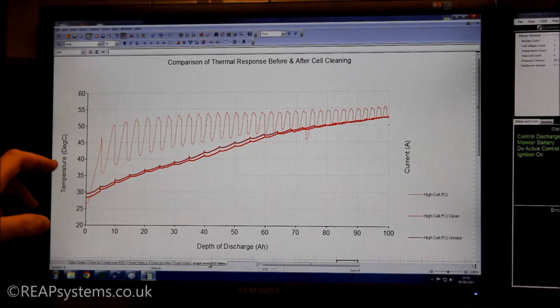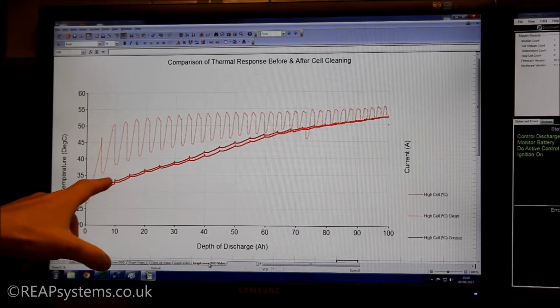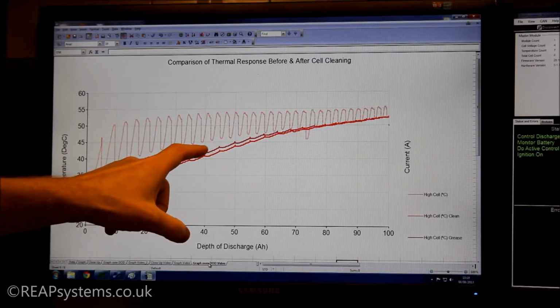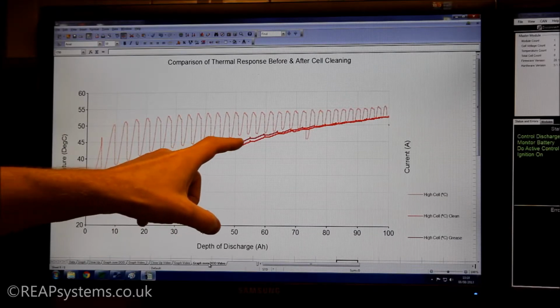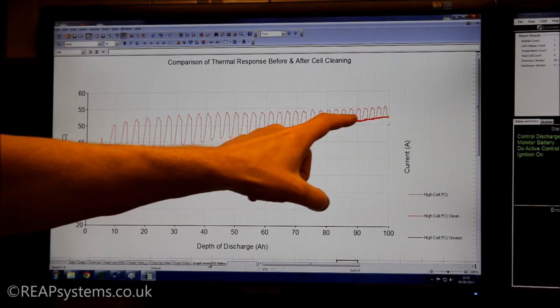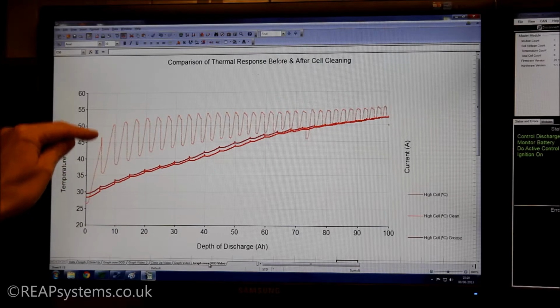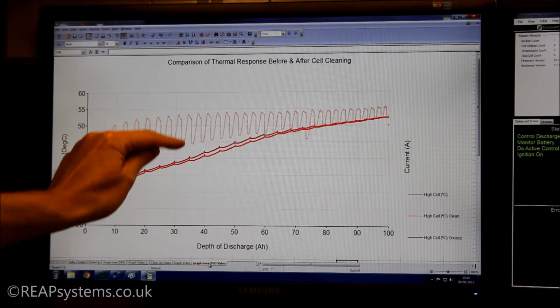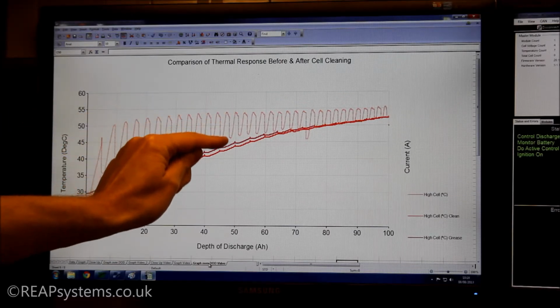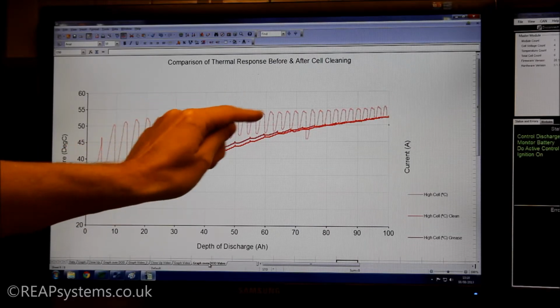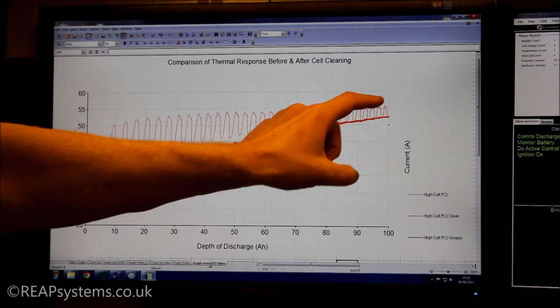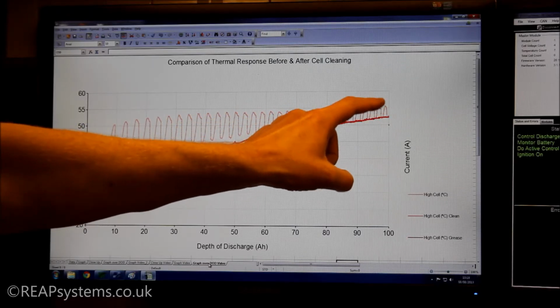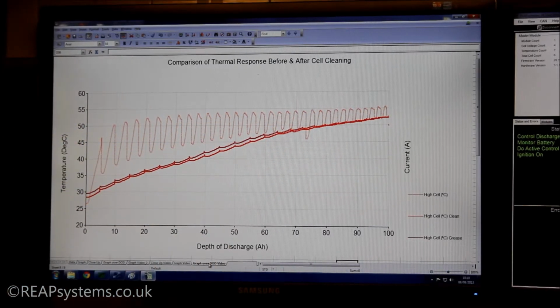Is it fair to say maybe that this here seems to be a true representation of the internal cell heating after cleaning the contacts, whereas this here is showing much more the heat generated at the contact, which is heating up quickly, and only towards the end, because the current levels are decreasing significantly here, is it showing more the internal temperature when we let it cool down a little bit? Yes, that seems a fair conclusion looking at this data.